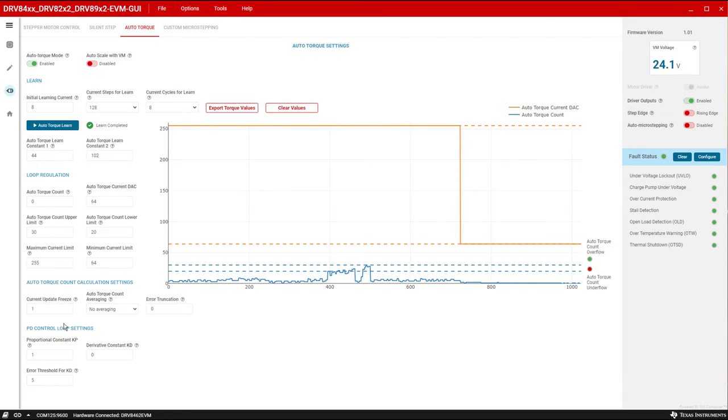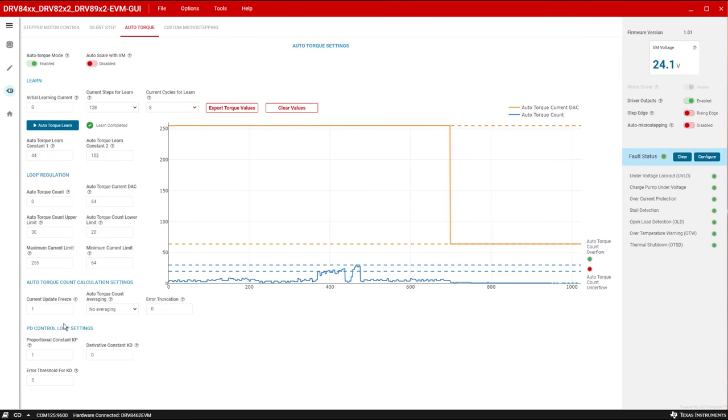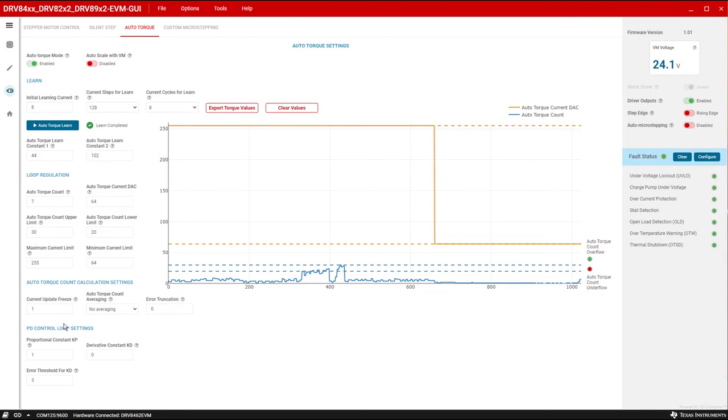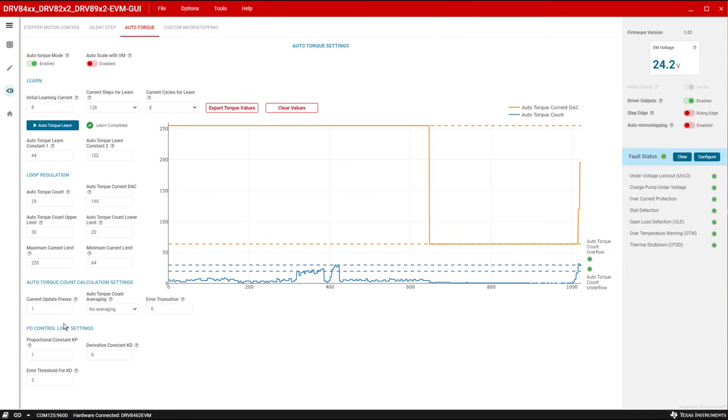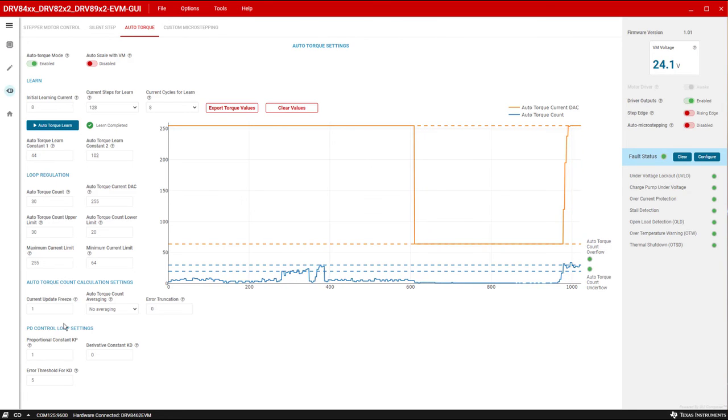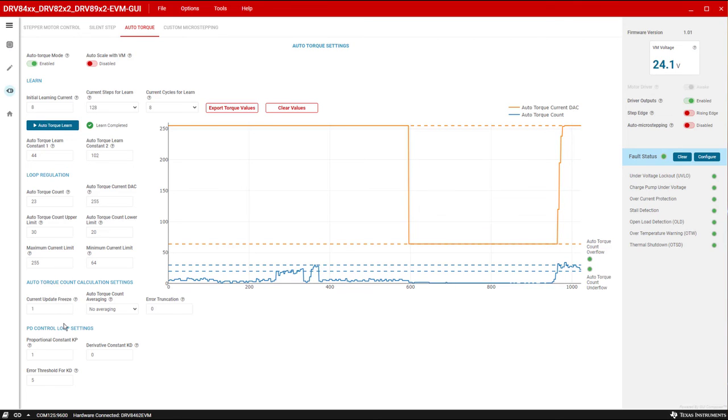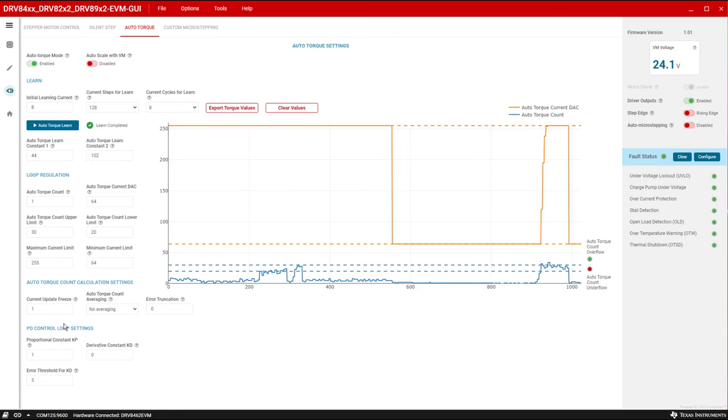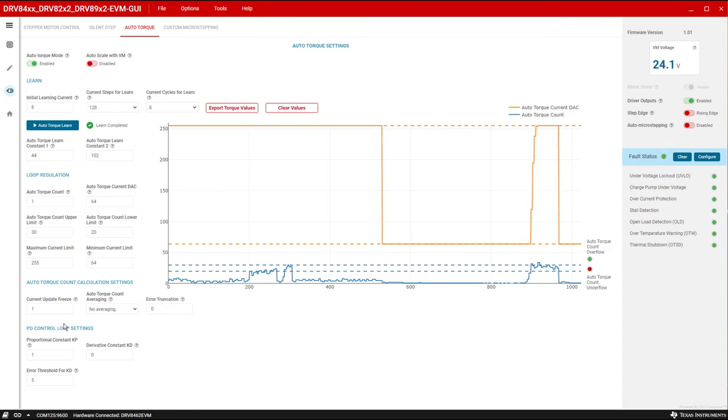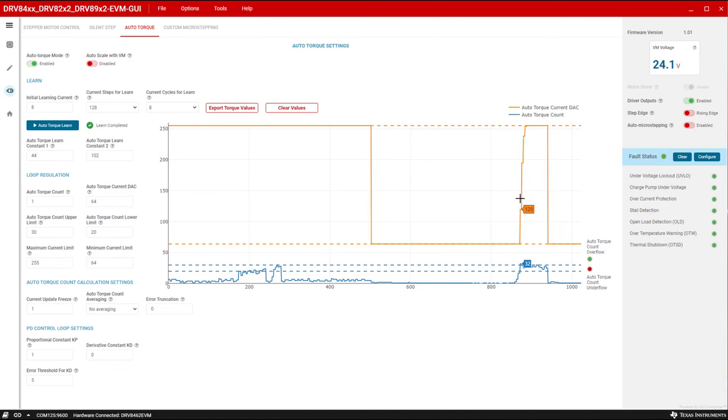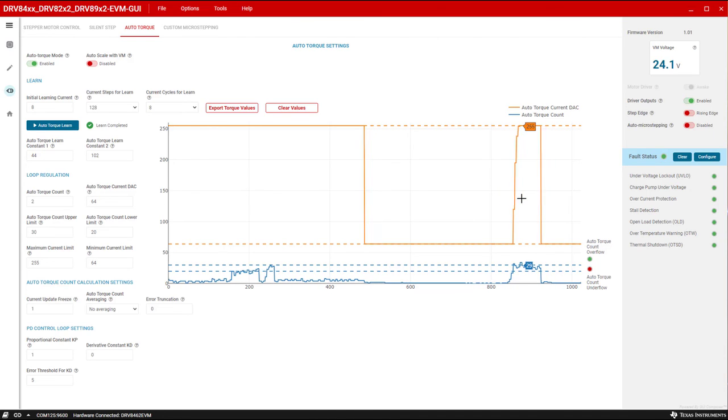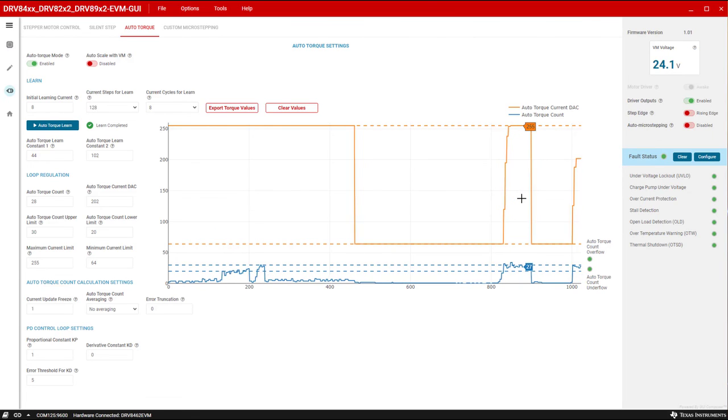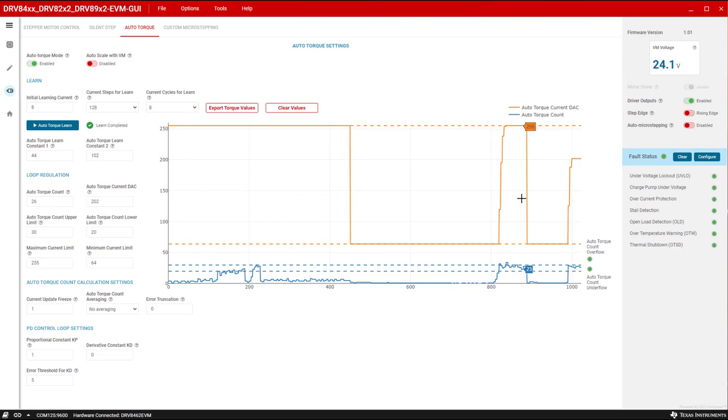The auto torque setup is completed. To perform a quick check, let's load the stepper with the maximum load torque of the application. The drive current will automatically change to the upper limit programmed. Now, let's load the stepper motor with the minimum load torque of the application. The drive current will quickly reduce to the lower limit programmed. This can be observed in the graph of the GUI. When the motor is loaded with nominal load torque, the drive current will be maintained within the defined hysteretic band.